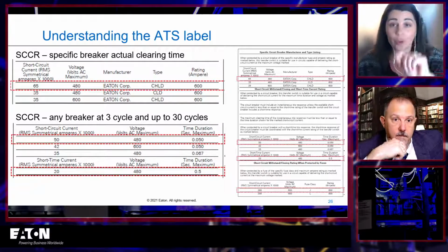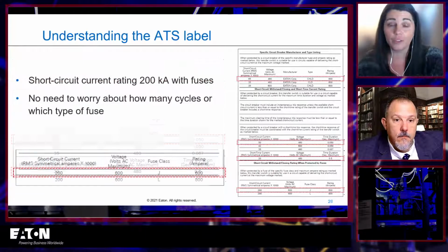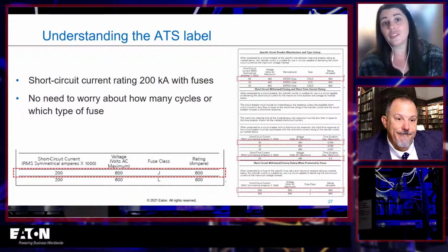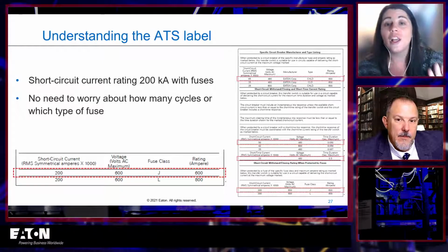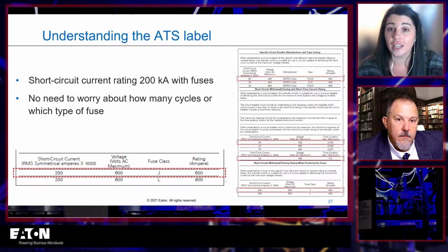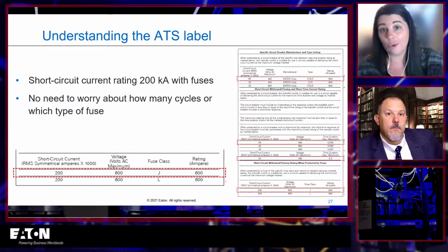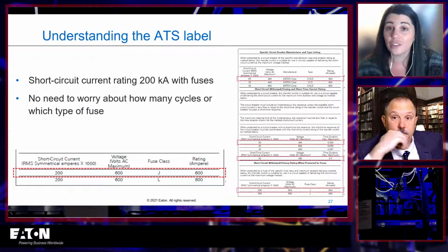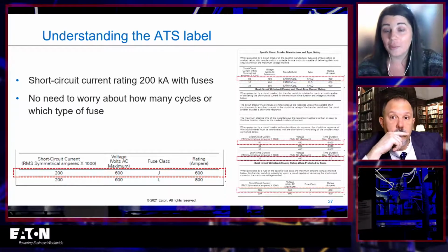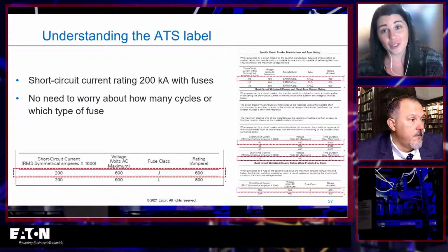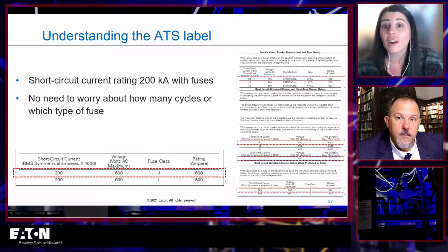And then there's another one, if you go to the next slide, for if there's a fuse in front of it. All right. So this is the label that tells you what the short circuit current rating is. And inspectors were saying, I don't want to have to, because whatever's feeding it may not be in the same room, right? So this is saying whoever installs it, you've got to look at this label and tell me what the short circuit current rating is, and you just have to mark it on the outside.